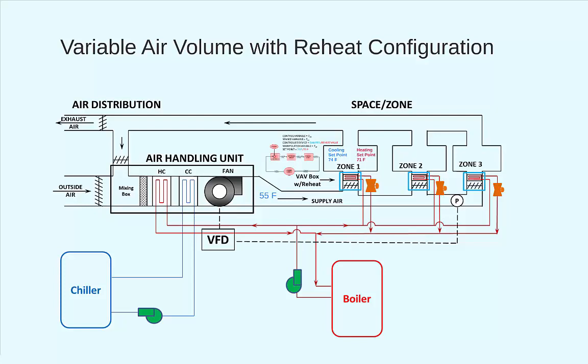During the spring and fall, there are days when one zone in the building may be requiring heating, while another zone may be requiring cooling. Thus, operating the system in the manner we just described allows us to provide heating to one zone and cooling to another. The ability to address this diversity of thermal loads in a building is a great attribute of VAV with reheat. But if it gets to the point where all the zones are requiring heating, what is the point of controlling the discharge air coming out of the air handling unit to 55 degrees Fahrenheit if all of that air is just going to be reheated at the various VAV boxes further downstream?